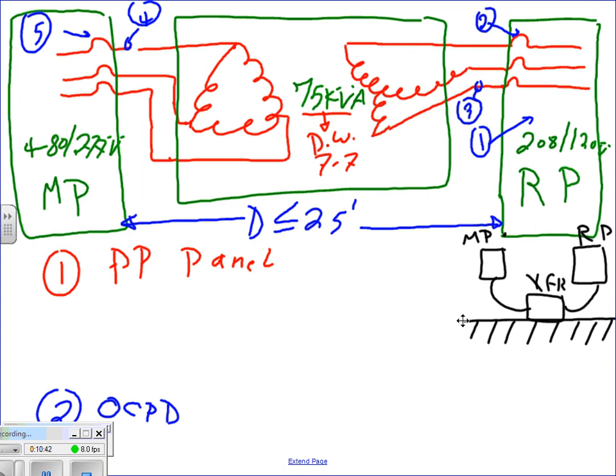The NEC reference is 450.14, page 352. In our case, that circuit breaker in the main panel is going to act as the disconnect because within 25 feet you can see it with no obstacles, so we're good to go.